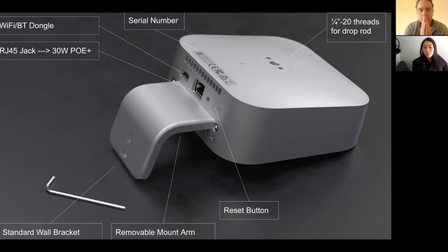An option is to remove the mount arm and drop the sensor from the ceiling with a 1/4 inch 20 threaded rod. And the lid of the sensor itself has the threads to take that rod. So much like any AV install that you're commonly installing, it just takes that and sits flush to the ceiling with a soft ceiling tile or hard ceiling, and all of that is included with our mount kit. What we don't provide in our mount kit is the rod itself, because we would need it to be cut to length depending on where it's prescribed to be dropped. So please make sure that you are bringing those if you are ceiling mounting them.